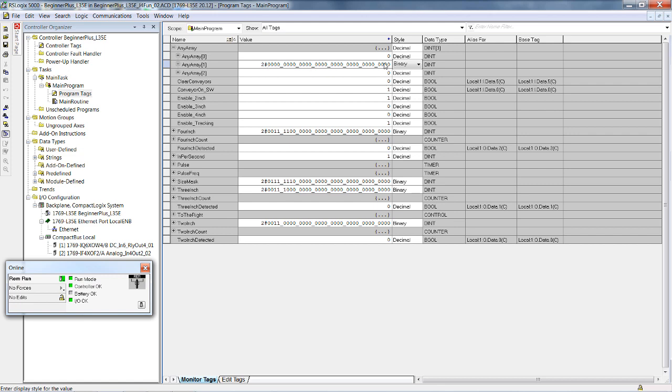This would be source A up here. This is the bit pattern of bit shifting on the conveyor, and we are specifically looking at bits 30, 29, 28, 27, 26, and 25. So our mask right here, these 6 on states, are comparing these 6 states with either a 2-inch pattern, a 3-inch pattern, or a 4-inch pattern to determine if we have detected a carton.